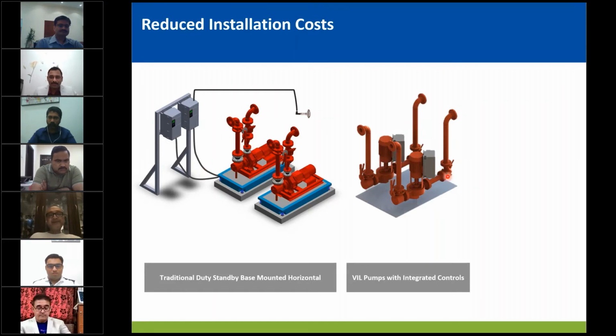And if you look at two integrated vertical inline pumps, the footprint is very, very low for an integrated pump like this. So integration is really saving you money, not only on initial cost for pump accessories like the inertia base and separate panel arrangement, but also on space. So probably you may need a smaller pump room or plant room for the pumps. Now, this is a small comparison of two pumps. If you had eight or more pumps, the savings achieved from this type of installation are going to be very, very significant.